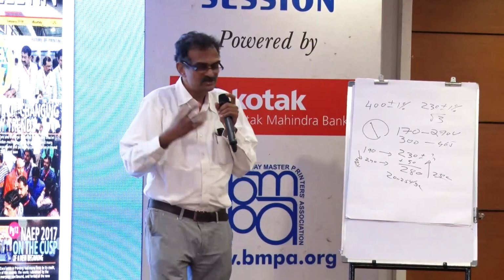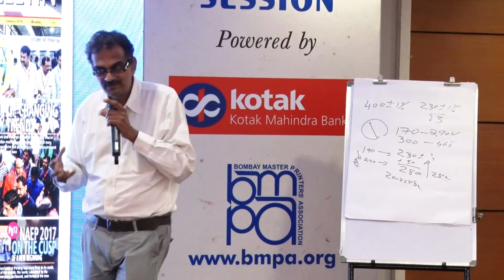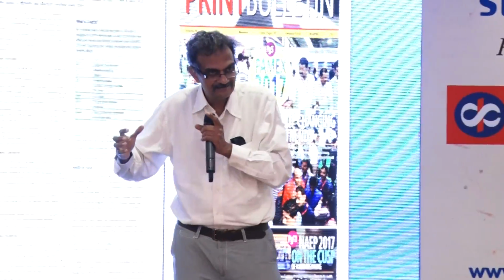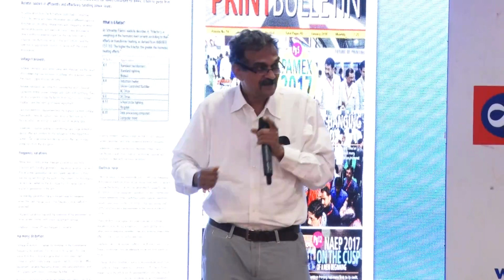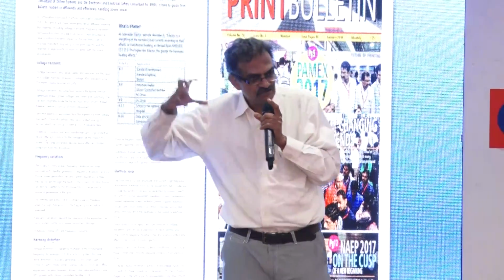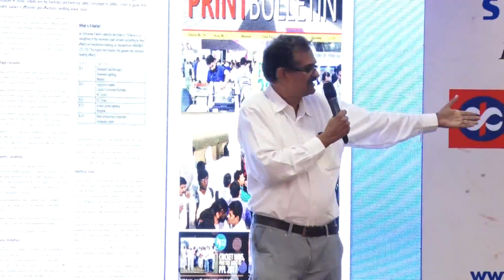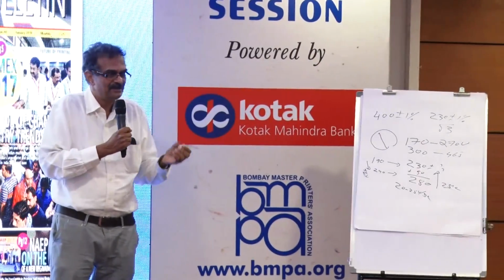If only the machine manufacturers were to share with us a system whereby I can isolate the supply to the brain, then I can put a very high and fast voltage correcting device just for the brain and allow the rest of the elements to work normally. Everything will work. But that's not really been happening. In very few machines have we been able to do that.